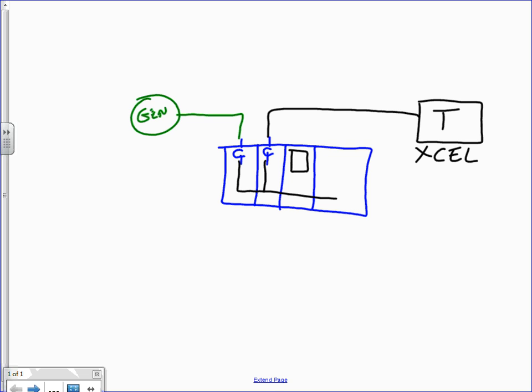So there's controls in here. Like the paralleling controls will identify the fact that I want to make this change. It'll fire up the genset. It'll control essentially the impedance and the sine wave, and it will sync that genset with the utility, and it controls it such that when our sine wave outputs are within a certain window of being in sync, it'll close that breaker onto the utility, and then it still controls even further the impedance of that genset, so that initially when they're closed, the load sort of stays on the utility, but then they can kind of ramp it up and walk the load over, it might take 5-10 seconds.